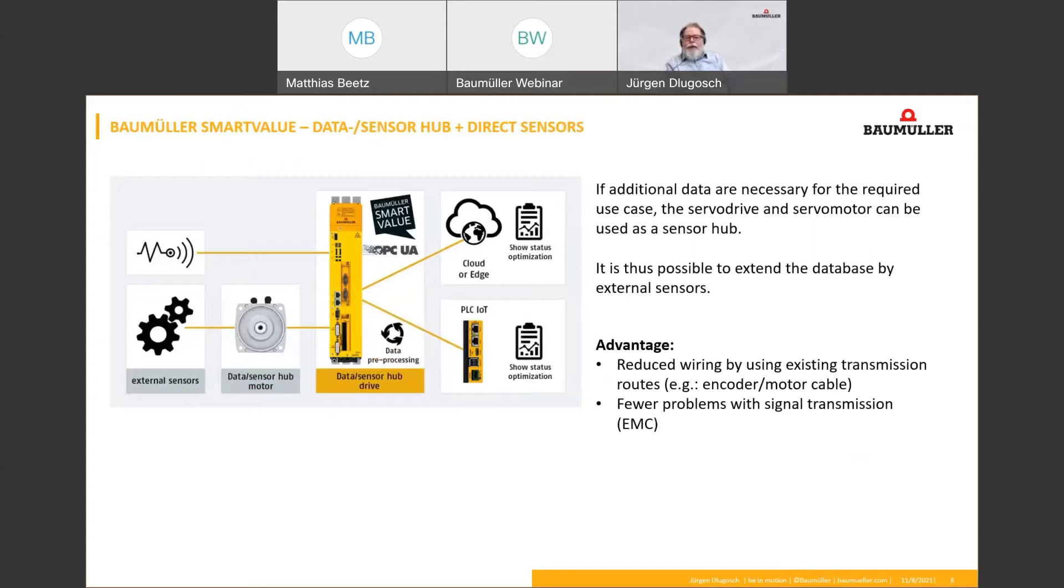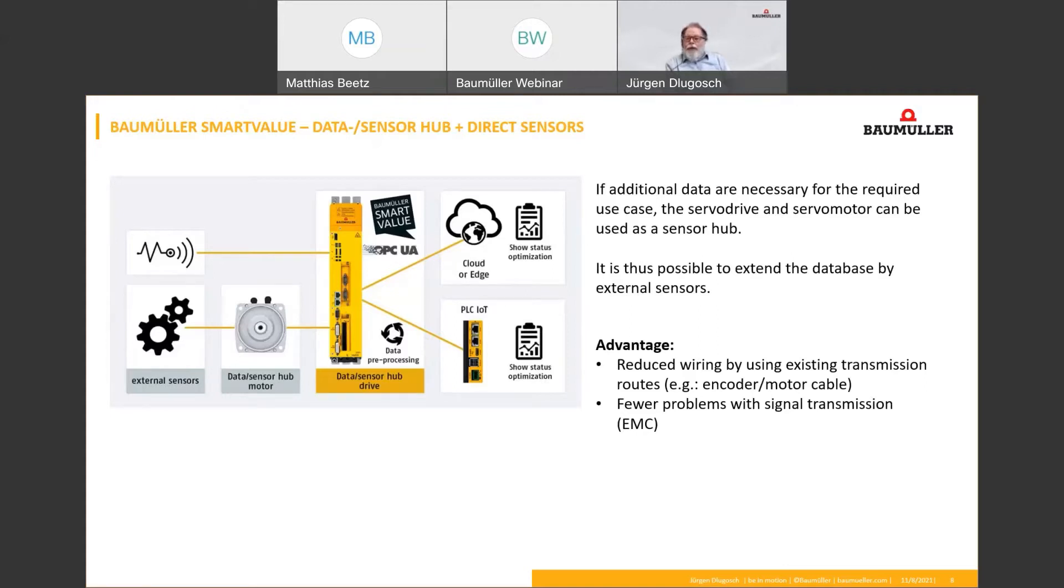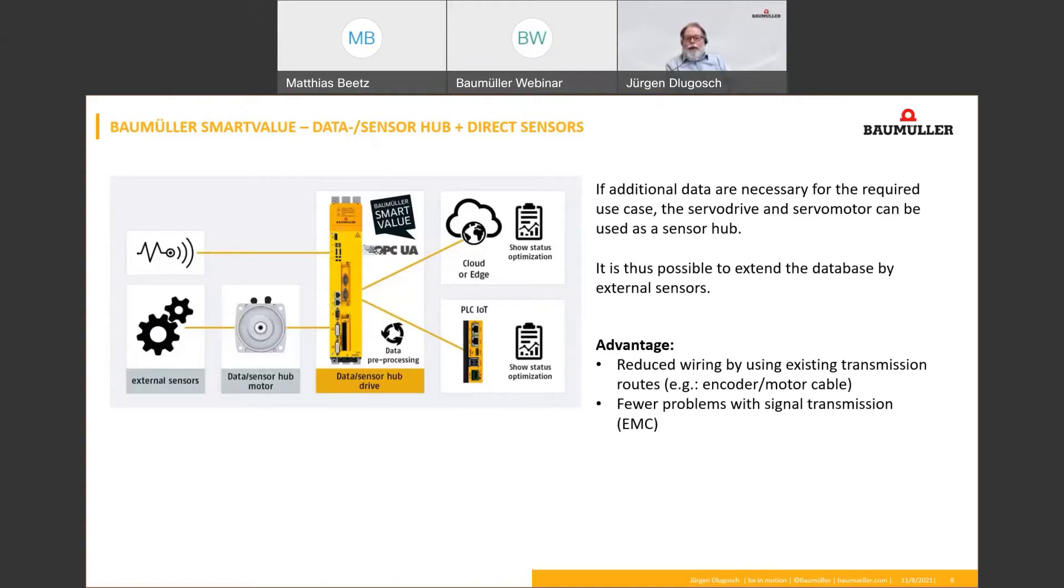How does the drive become a sensor hub? The existing analog and digital inputs of the drive can be used for connecting direct sensors on it. So the drive will be acting like a sensor hub. These signals can be pre-processed by the drive and can also be distributed to IoT nodes. So the drive is also operating like a data hub. By using modern technology like digital encoder with single cable solution, the sensor signals can be transmitted via the encoder cable. And at least, also the motor itself can be served as a data or sensor hub.